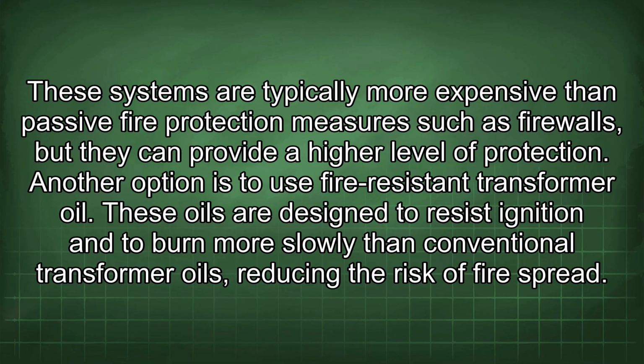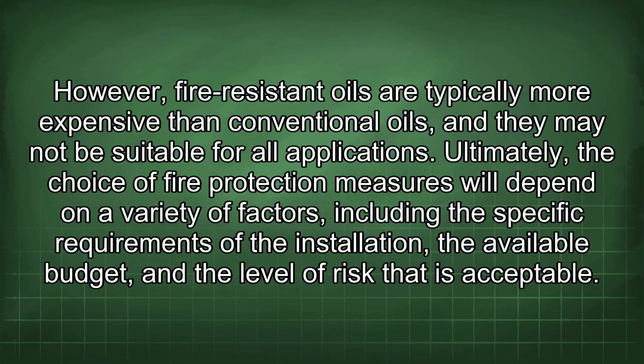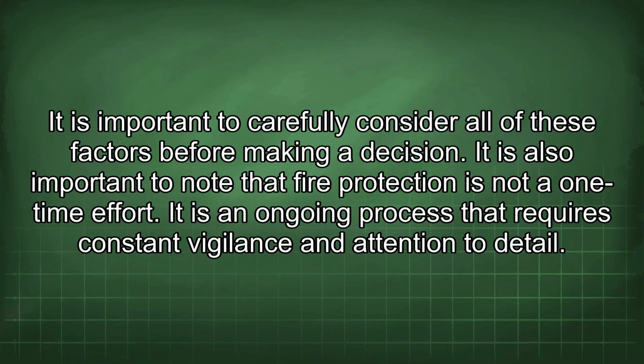These oils are designed to resist ignition and to burn more slowly than conventional transformer oils, reducing the risk of fire spread. However, fire-resistant oils are typically more expensive than conventional oils, and they may not be suitable for all applications. Ultimately, the choice of fire protection measures will depend on a variety of factors, including the specific requirements of the installation, the available budget, and the level of risk that is acceptable. It is important to carefully consider all of these factors before making a decision.